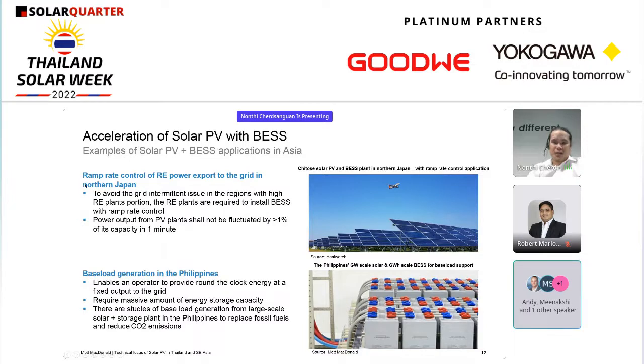The first case is Japan, where there's an aim to increase renewable energy's portion of generation, especially in the northern area like Hokkaido. To address potential grid intermittency issues from high portions of renewable energy, a BESS system with ramp rate control applications is installed together with the renewable energy plants, aiming to smoothen the power export and limit fluctuation within certain criteria. In northern Japan, the power output fluctuation must not exceed 1% of plant capacity within 1 minute, and that's the role of the battery energy storage system.